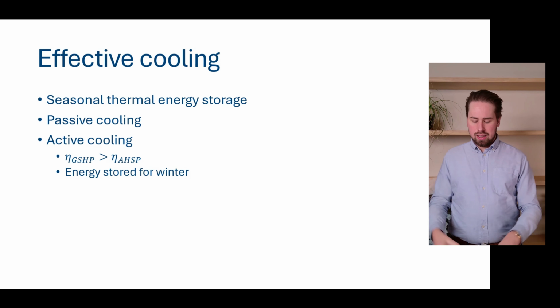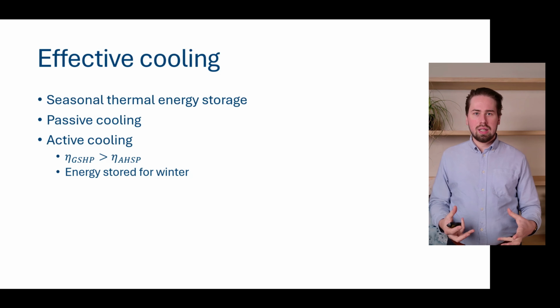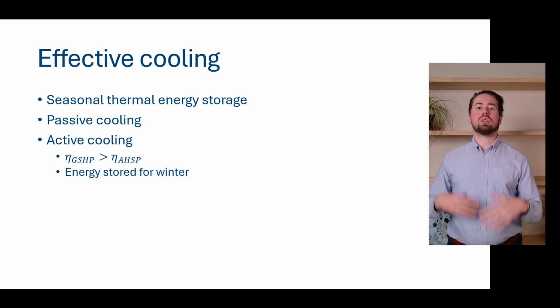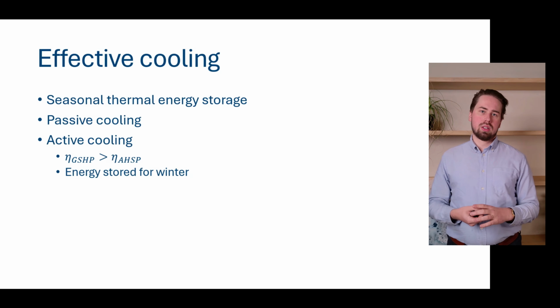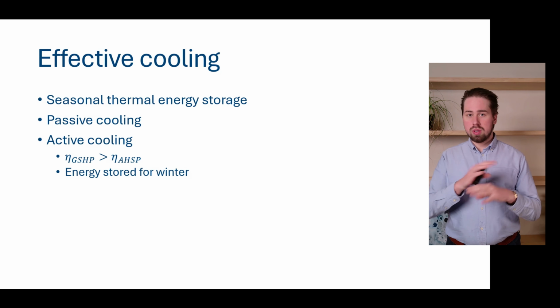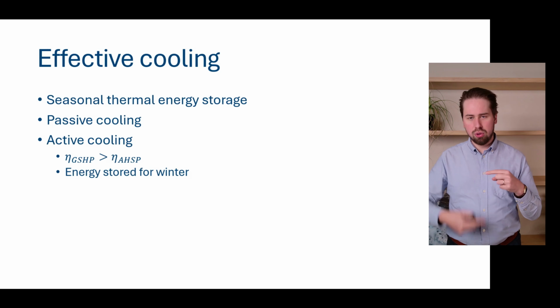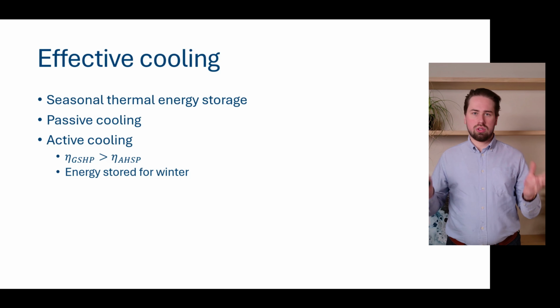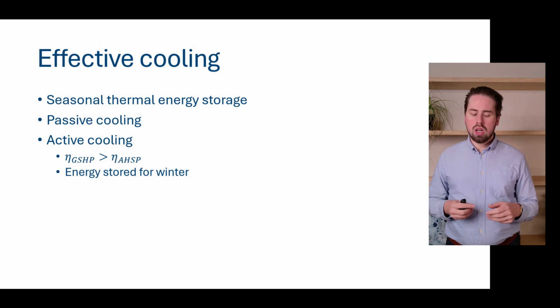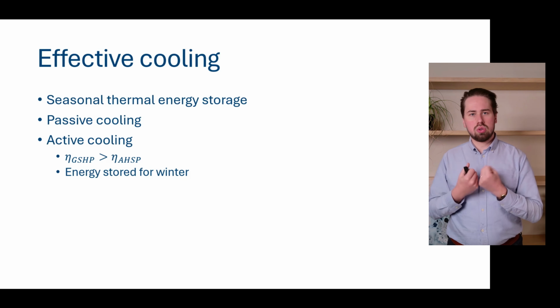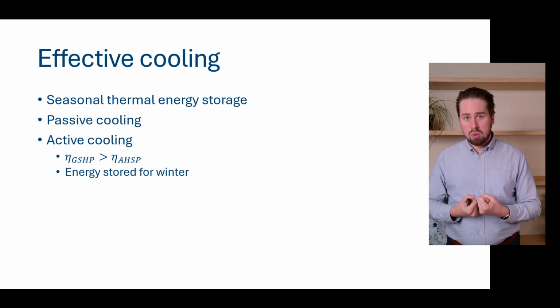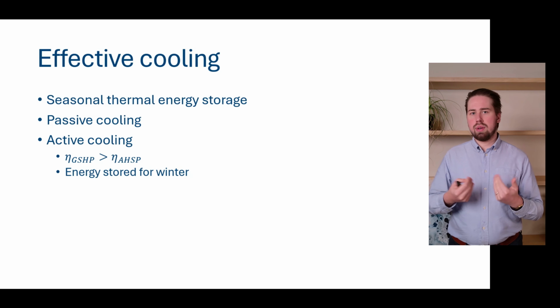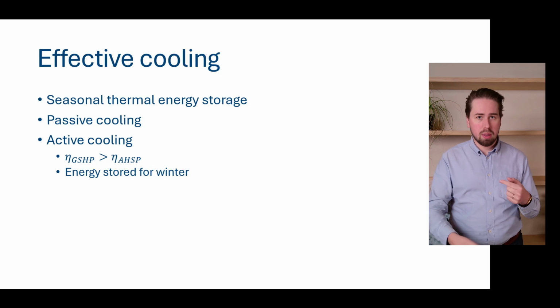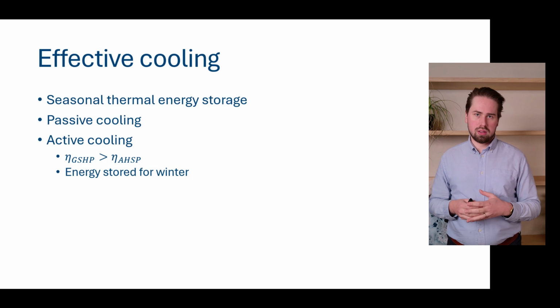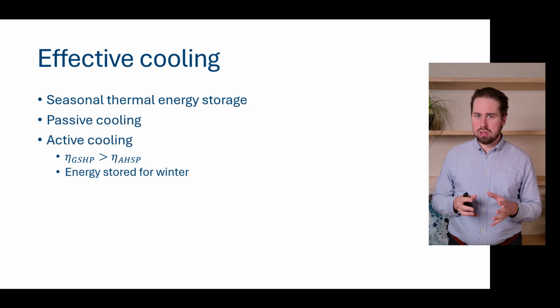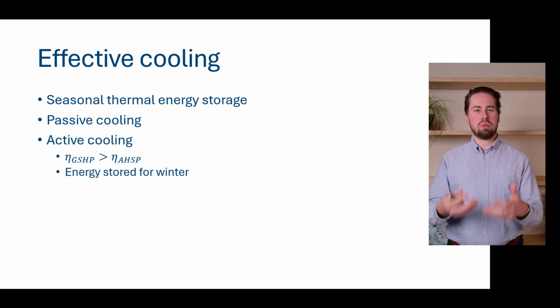But in the ground, if we extract the heat, the ground cools down. And this stored cold we can use for passive cooling or free cooling in summer. By this we mean that we don't need our heat pump for cooling. We just circulate a fluid through the ground. And since our ground is at 10, 12 degrees Celsius, we can use this cold directly to cool down our building in a passive way, which is also almost free. It is a very, very high efficiency because only a circulation pump is running to keep the fluid flowing through the borefield.